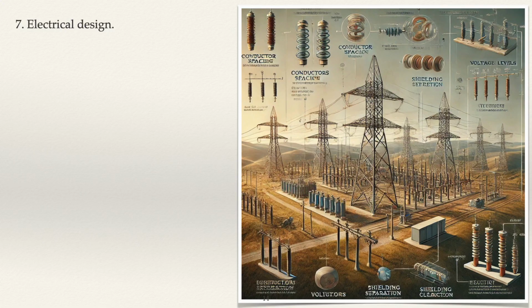Second, inductance. The magnetic field around the conductor causes inductive reactance, which can result in power losses. Proper spacing and bundling of conductors help minimize inductance. Third, capacitance. Capacitance between conductors and the ground can lead to reactive power losses. Optimized tower design and conductor spacing reduce capacitance effects by use of bundled conductors to balance inductive and capacitive reactance. Selection of conductor size and material to optimize transmission efficiency.